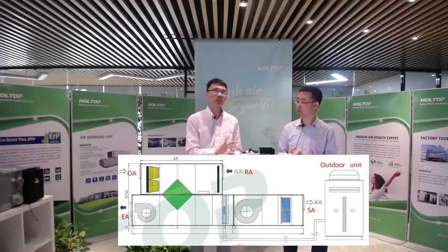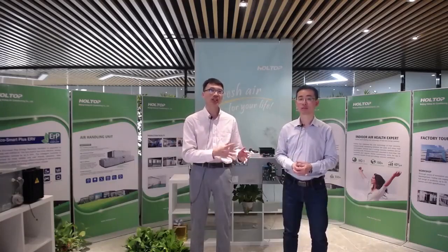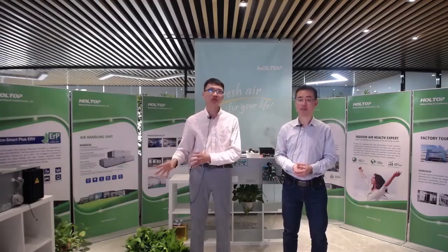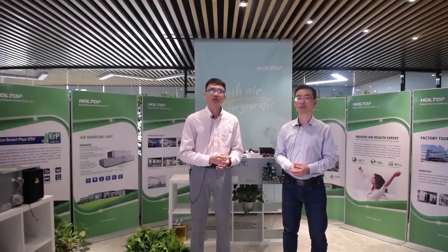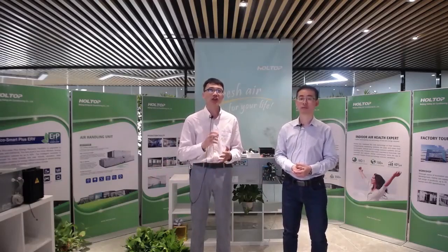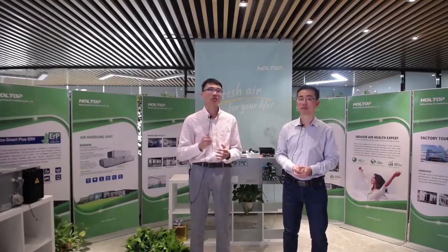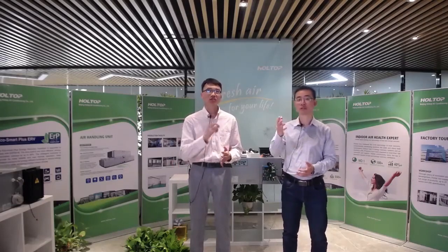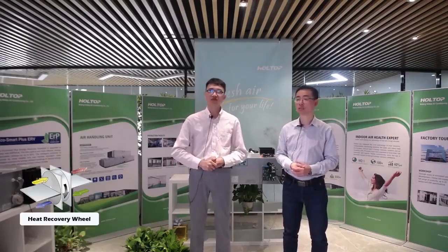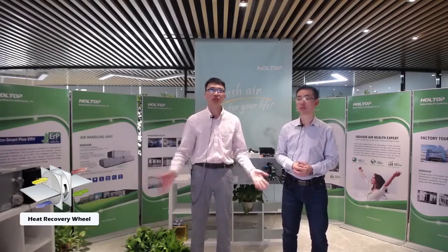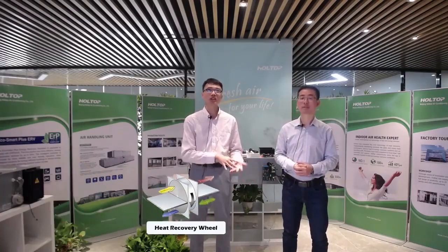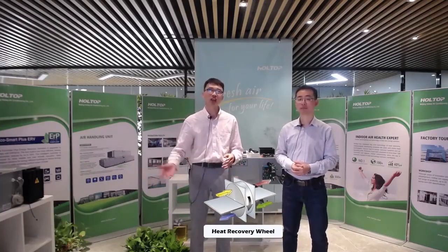First, as we know, the air-to-air heat exchanger is the key component to recover energy from the indoor extract air and send the energy back to the fresh air. Holtop has dedicated efforts to develop the most efficient air-to-air heat exchangers for almost 9 years. So far, we have the following kinds of air-to-air heat exchangers. First of all, let's show the picture of the heat recovery wheel. From this picture, you can see a rotary wheel heat exchanger, both for sensible and enthalpy.